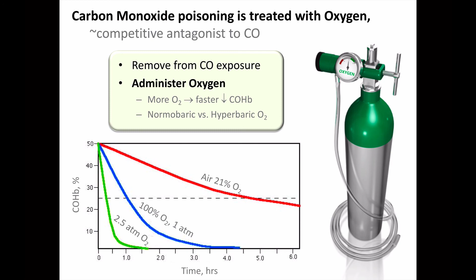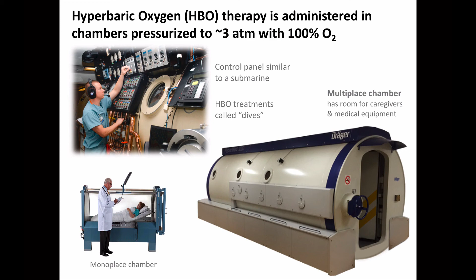Hyperbaric oxygen, or HBO therapy, is administered in chambers that can be pressurized up to about 3 atmospheres with 100% oxygen. The control panel and the chamber itself can often resemble a submarine, and the treatments in the chamber are also called dives, as if the people inside are diving underwater to higher pressure zones. Here we see a multi-place chamber, which is big enough for multiple patients and sicker patients who may need to be accompanied by medical staff or equipment. Hyperbaric monoplace chambers also exist, but they most commonly are used for other indications in non-poisoned stable patients who don't need any fancy equipment or caregivers in with them.